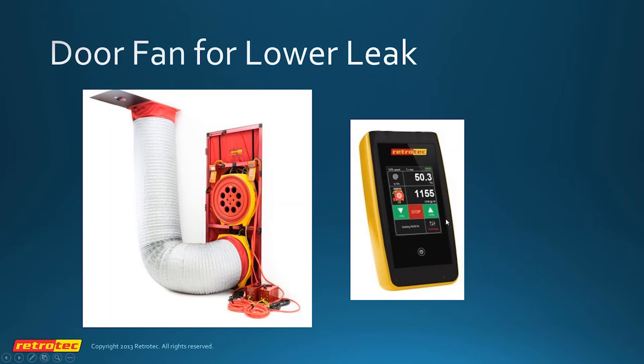The new gauges that we have, with the DM2 and the DM32, have a really cool feature, which is called set to zero. So you can measure the pressure across the suspended ceiling, and you can ask the software or ask the gauge to set the pressure to zero. It balances the room out. All the fans will balance themselves, and you can get a reading very quickly. What we used to do in the old days is have two people, one that was adjusting the fan, the other was putting smoke across the tiles and determining whether the smoke was moving up or down. This is a much better and faster system and requires only one person.